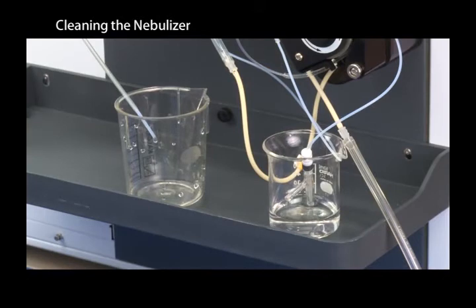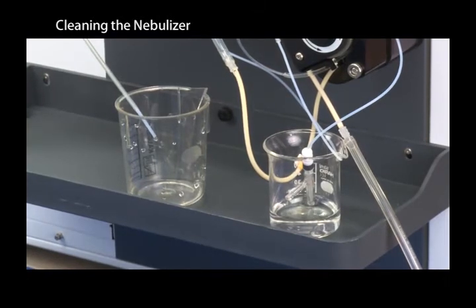Run the peristaltic pump at high speed and flush pure water from the nebulizer tip toward the sample uptake for a few minutes.